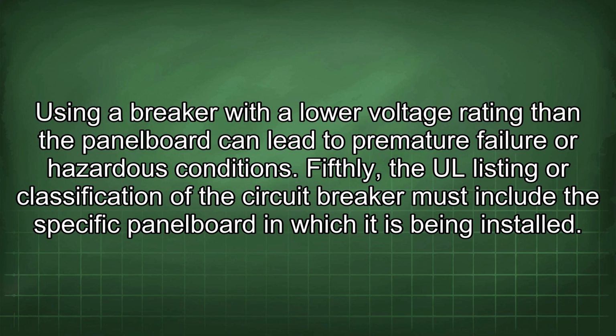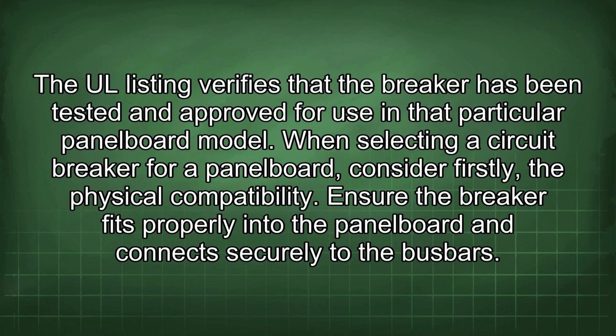Fifthly, the UL listing or classification of the circuit breaker must include the specific panelboard in which it is being installed. The UL listing verifies that the breaker has been tested and approved for use in that particular panelboard model. When selecting a circuit breaker for a panelboard, consider firstly the physical compatibility. Ensure the breaker fits properly into the panelboard and connects securely to the bus bars.